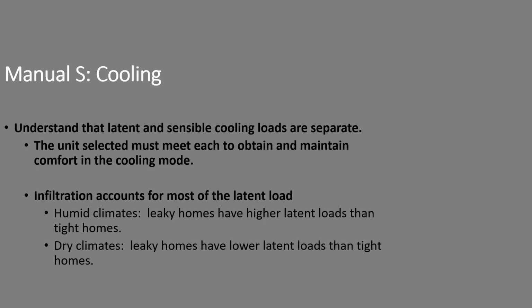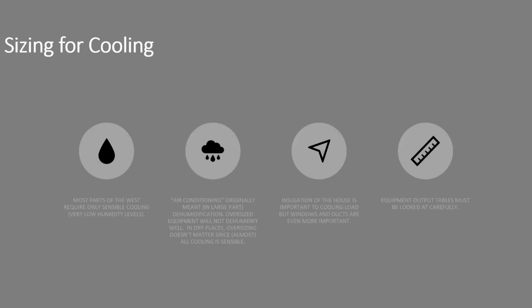Manual S cooling, understand those two loads are separate. Again, what's interesting is in other parts of the country, if you have a leaky house, the latent load increases because of all the humidity outside. In dry climates like ours, that leaky home, actually the air is so dry that the leakiness actually dries it out further. There are 4 important things to remember when sizing for cooling. Again, once again, we live in the great Northwest where we don't have to worry about dehumidification. That's the good news. Air conditioning originally meant you have to reduce the latent load and the sensible load.